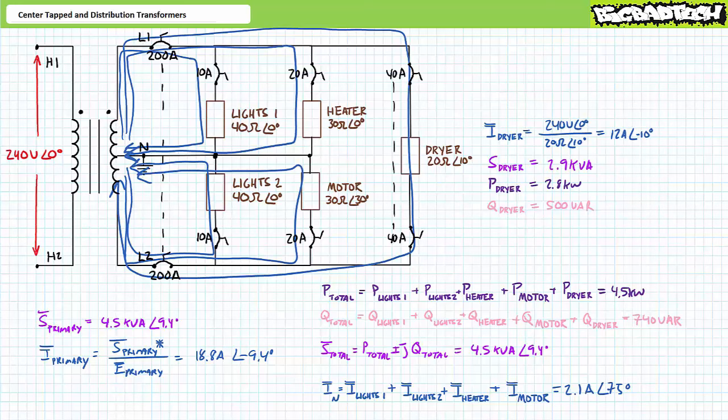You note the single phase loads require the neutral line to function as intended. As these examples illustrated, any imbalance between L1 and L2 results in current traveling in the neutral line. Only in the very rare occasion with equal loads on the opposite phases does it result in no current traveling in the neutral line. This is one of the compelling reasons circuit breakers make or break connection with the hot or high side of the distribution transformer rather than the neutral line. With the system in its present condition, the single phase loads experience exactly 120 volts and the dryer experiences 240 volts.